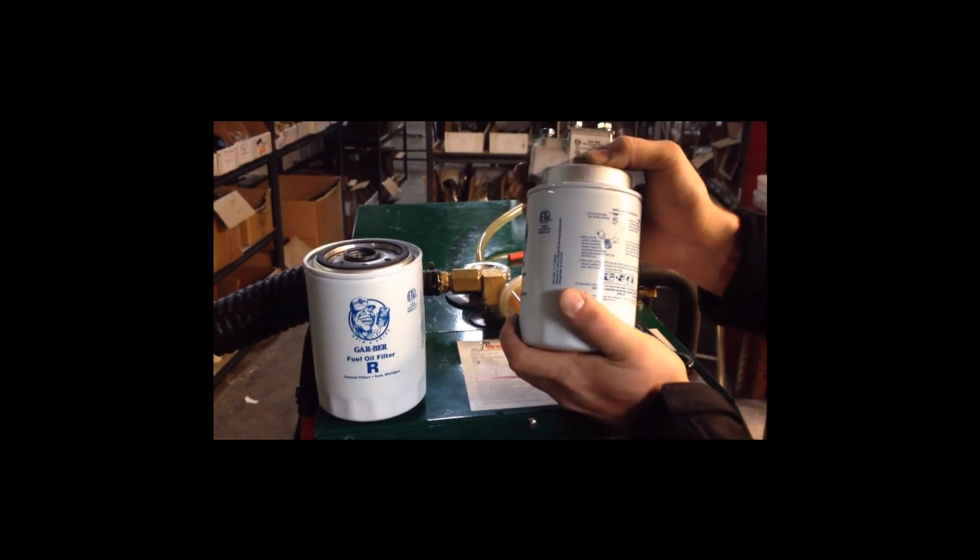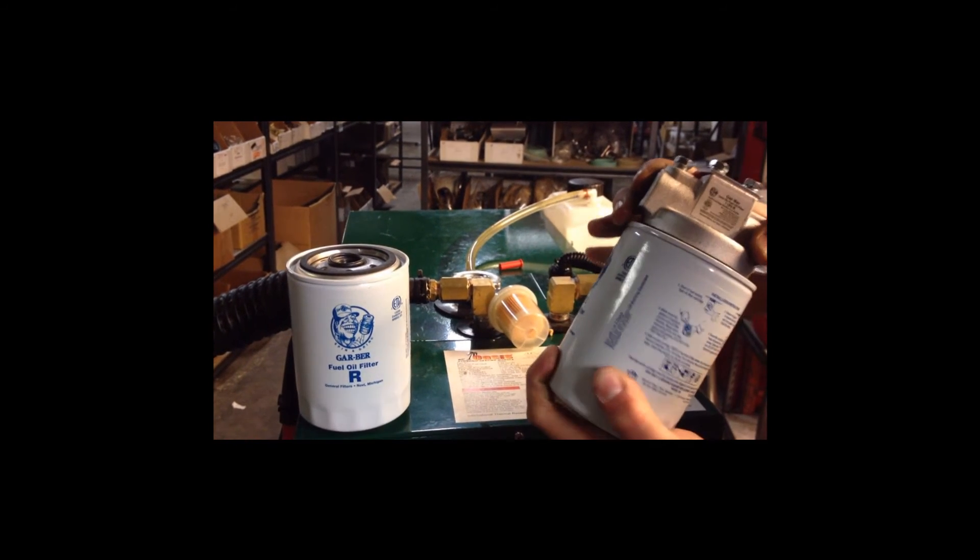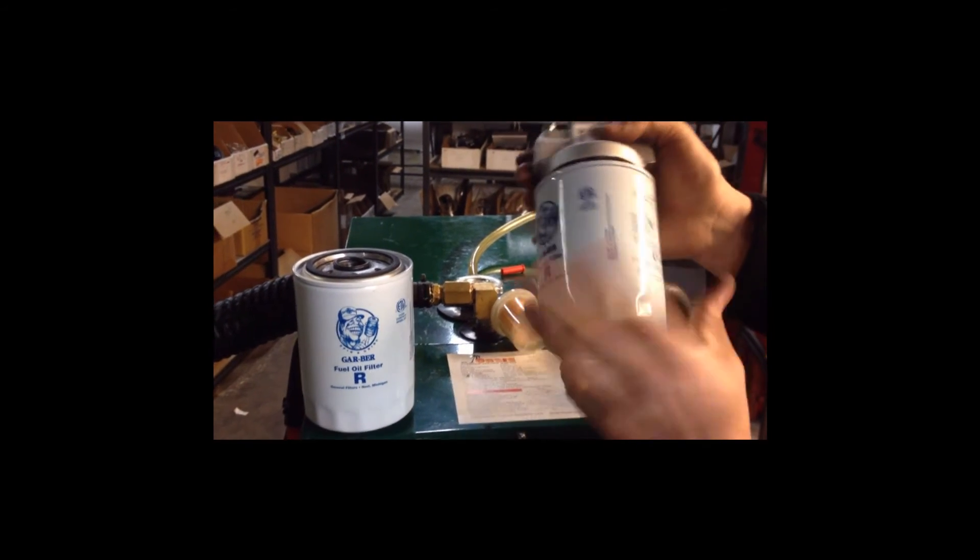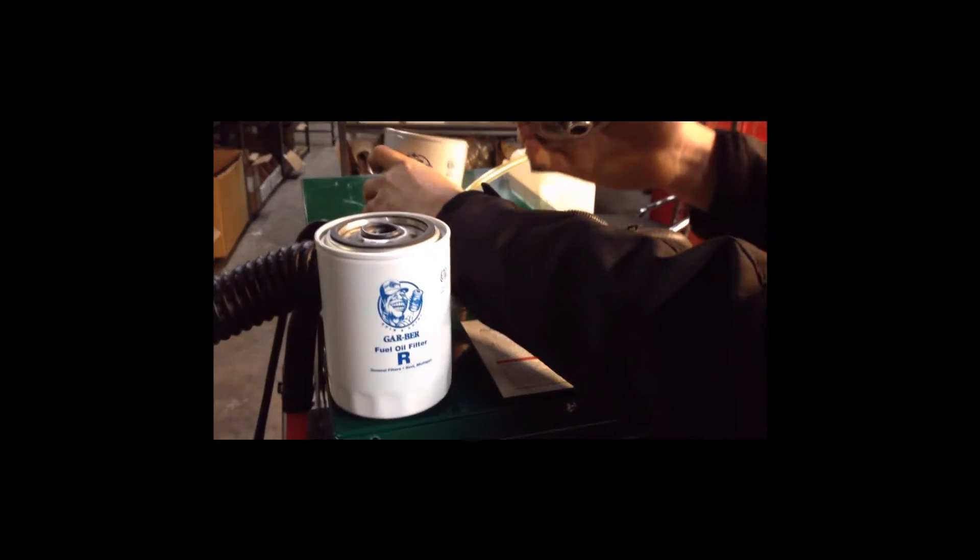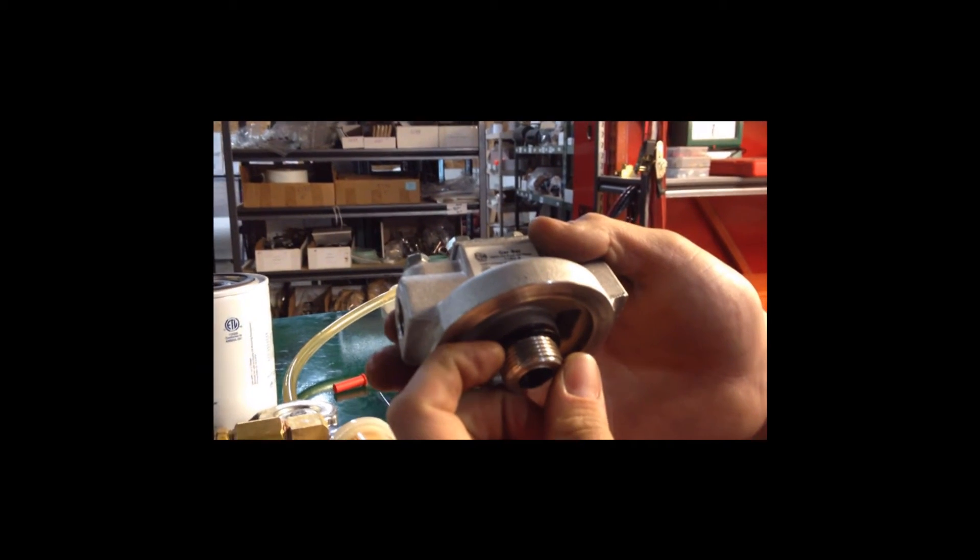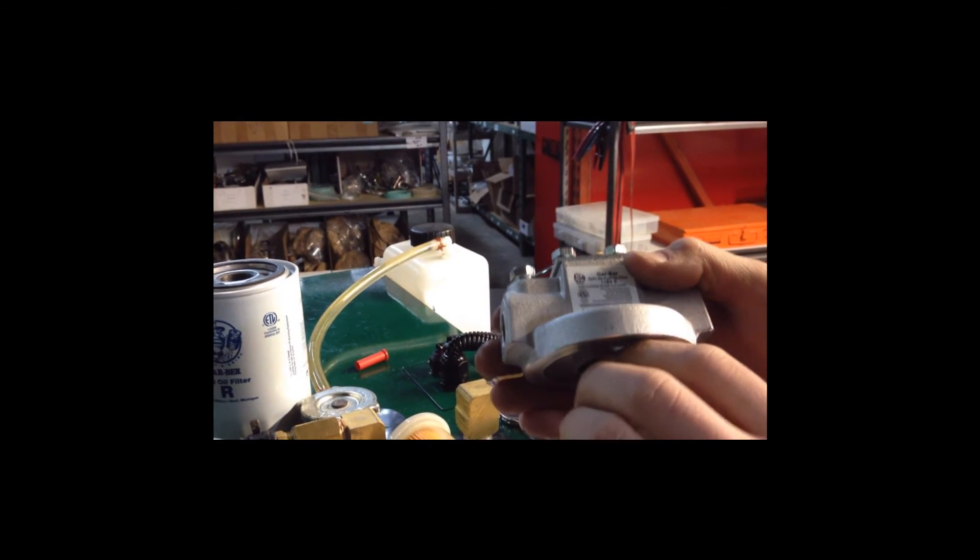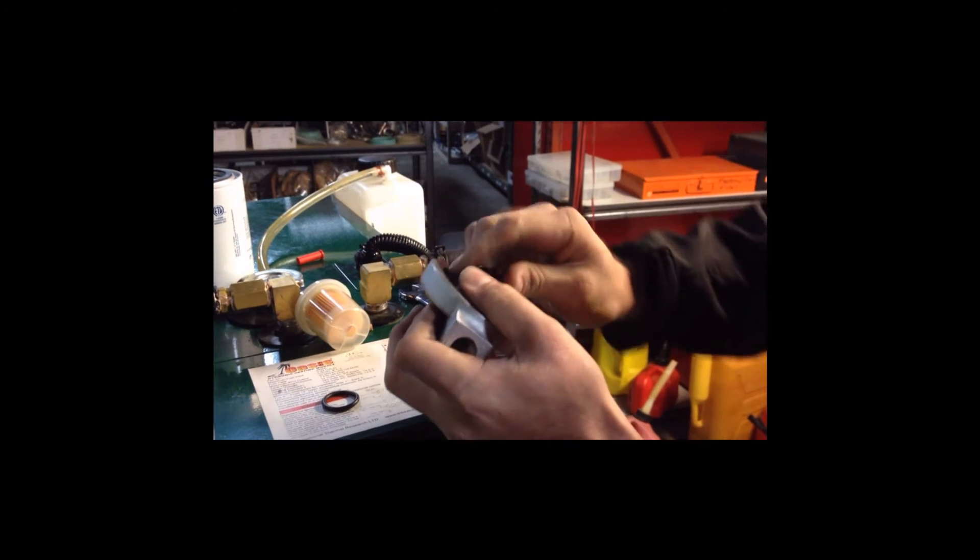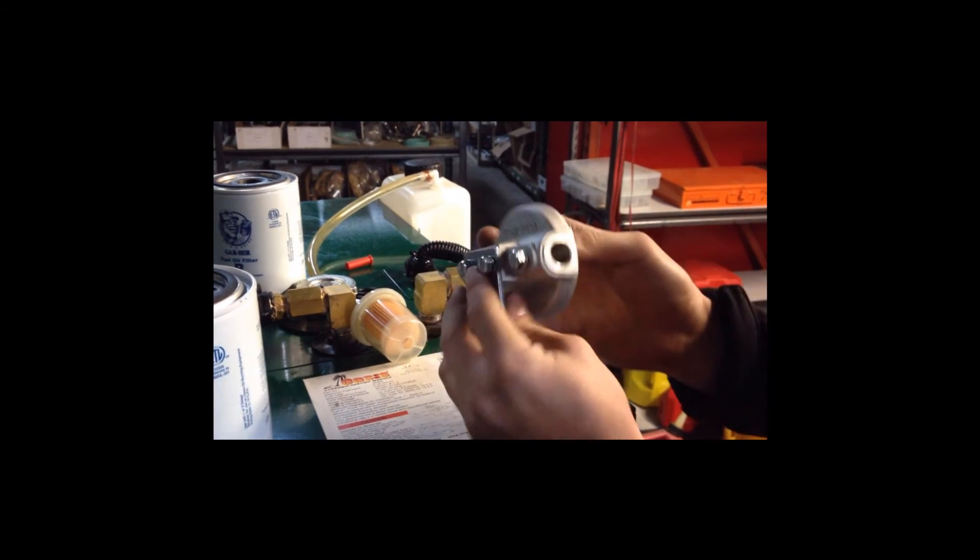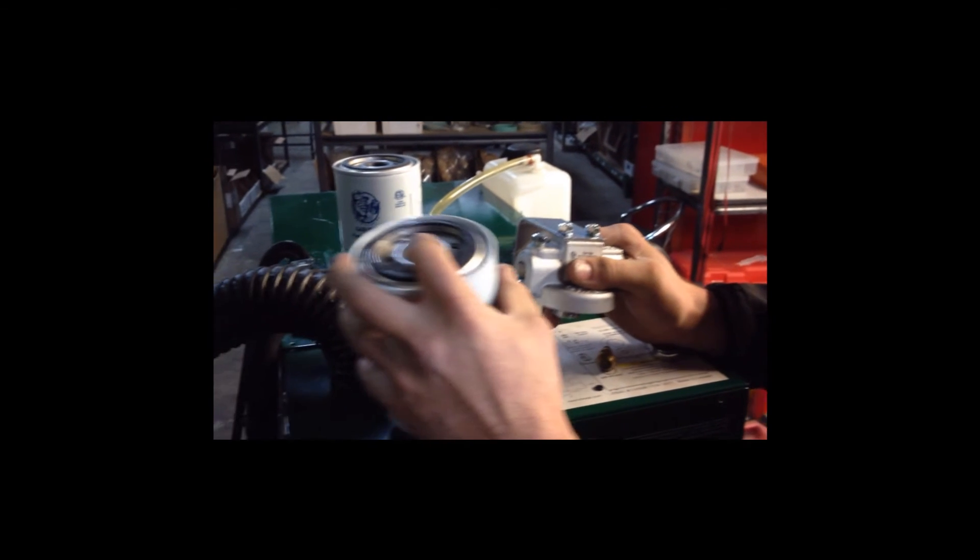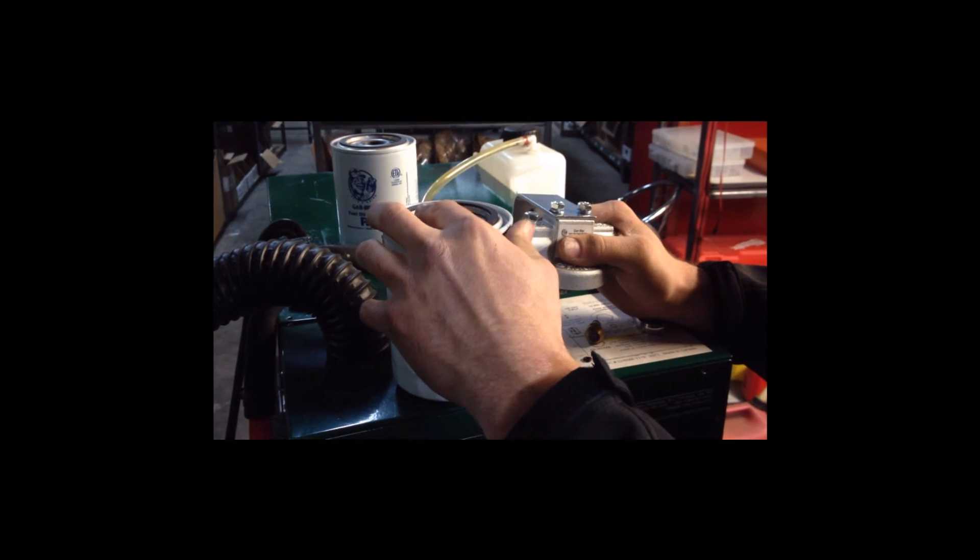Now sometimes you are able to just undo these by hand. Other times you might need to use a filter wrench. When you remove the filter, notice on the bottom side of the filter housing there is an O-ring that needs to be replaced. Remove that O-ring and replace it with the new one that comes in the kit. And if you have diesel fuel handy, you are going to want to fill your filter before installing. This will prevent flame out.